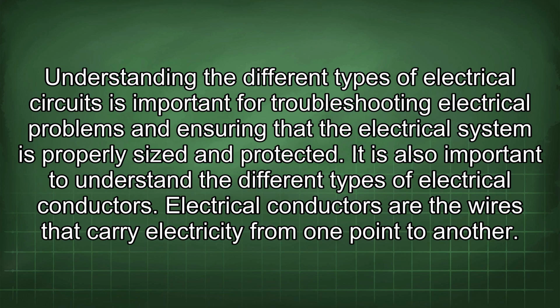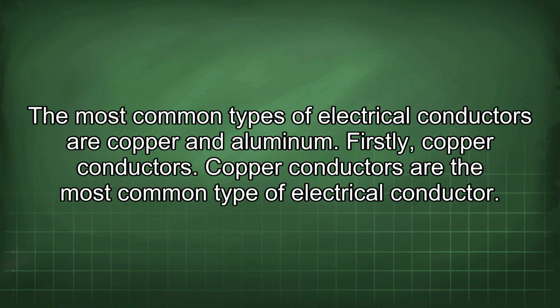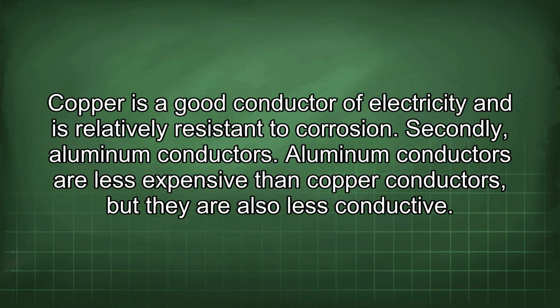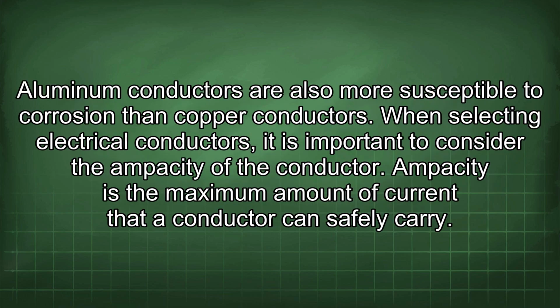Understanding the different types of electrical circuits is important for troubleshooting electrical problems and ensuring that the electrical system is properly sized and protected. It is also important to understand the different types of electrical conductors. Electrical conductors are the wires that carry electricity from one point to another. The most common types of electrical conductors are copper and aluminum. Firstly, copper conductors. Copper conductors are the most common type of electrical conductor. Copper is a good conductor of electricity and is relatively resistant to corrosion. Secondly, aluminum conductors. Aluminum conductors are less expensive than copper conductors, but they are also less conductive. Aluminum conductors are also more susceptible to corrosion than copper conductors.